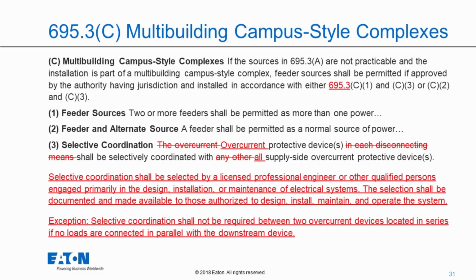When we look at fire pumps, it's very common to have a scenario where we have a multi-building campus and we have a feeder overcurrent device that supplies several other buildings' fire pumps. And this just basically states that those overcurrent devices must be selectively coordinated with all supply-side overcurrent devices. So they kind of deviated from what we do for elevators by talking about just the disconnecting means for the fire pump. They now basically have this more as a system approach. And as you can see, they added the text about the requirement that the selection be done by a qualified person, and it must be documented.